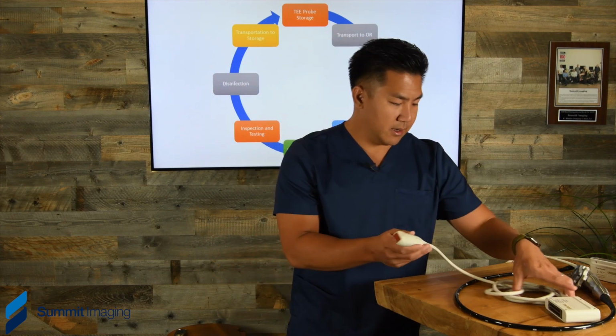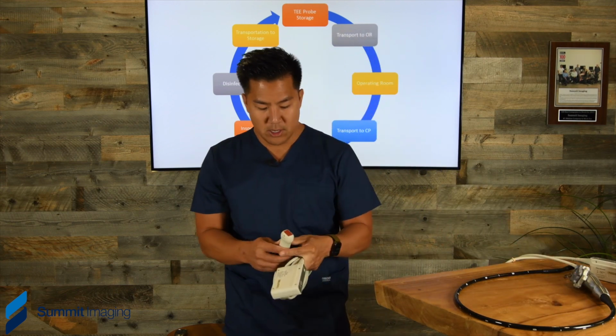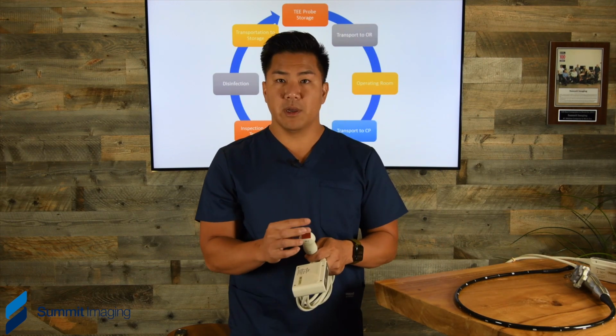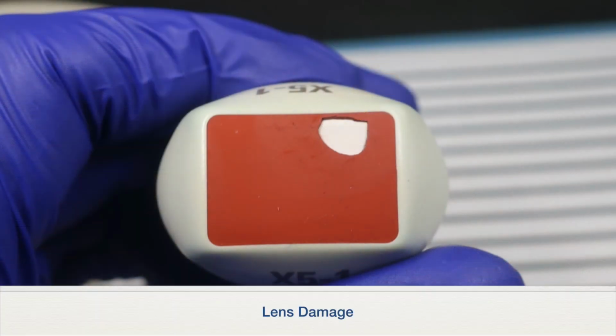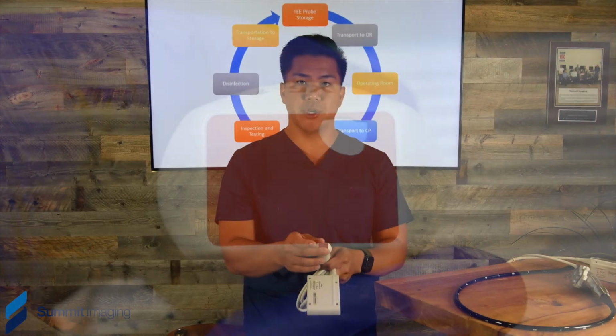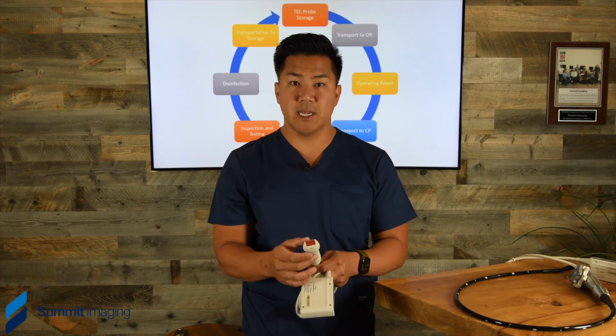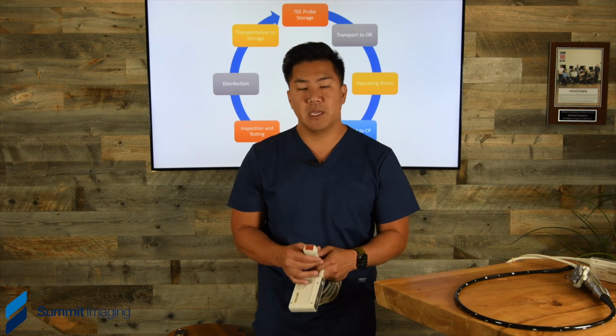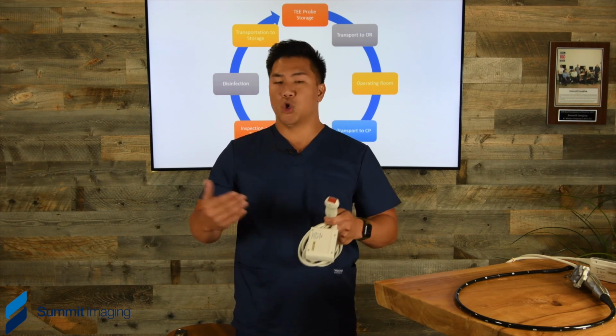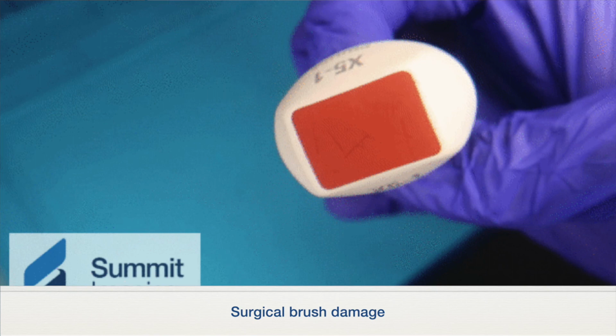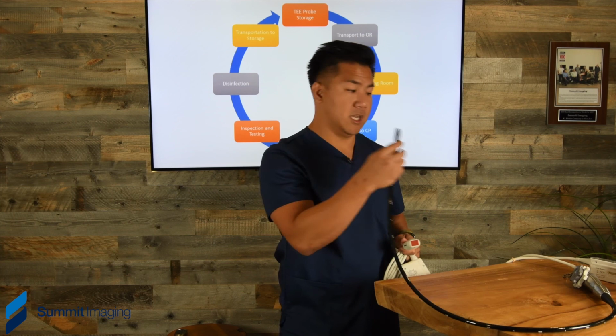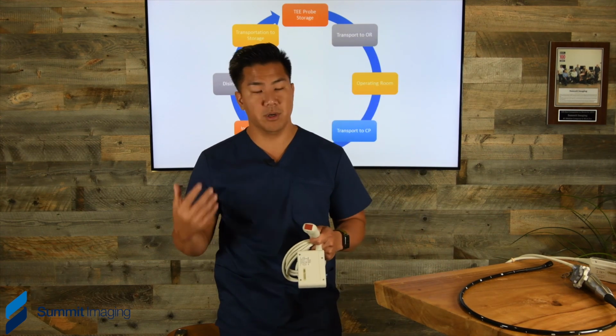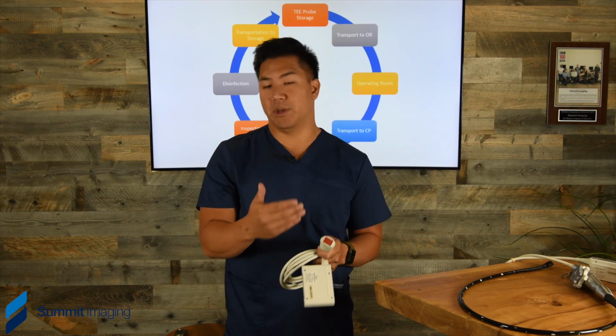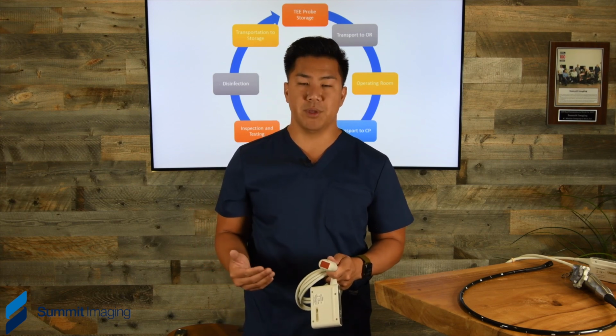Now, when we're inspecting a traditional transducer, we really want to look at the lens and see if there's any lens damage. Everything from gapping and peeling of the edges to small lacerations and cuts on the surface of the lens. We're seeing a couple things. Surgical brushes do not belong on the face of these probes. They should not be used on the tips of these probes. These surgical brushes are really abrasive, and this equipment just isn't built to take that kind of abuse.